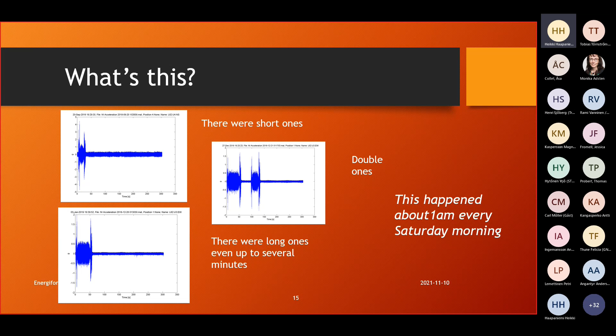I have another case here. This is actually a pipe beside a pump, and it happens that transients occur at different places in this pipe system at different times. It wasn't due to the same occasion, but due to something else. We're not finished with this, but we think it's due to bubbles in the system and different temperatures, causing an occasional implosion of a steam bubble.